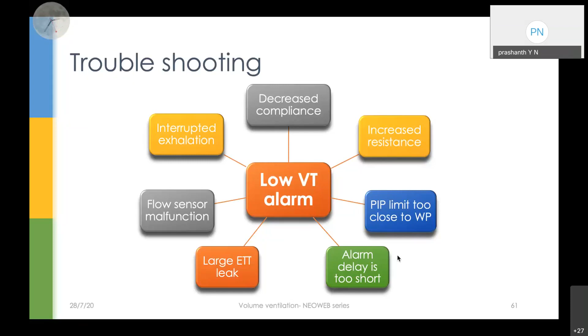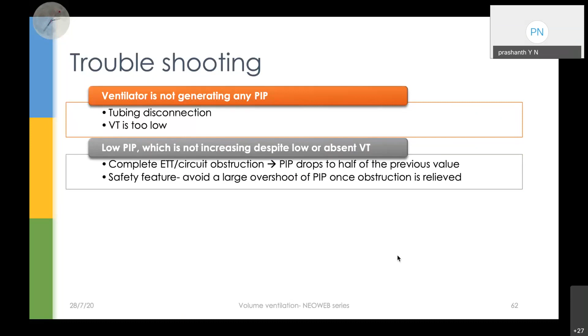All right. Other things could be, you also would have seen that a ventilator is not generating any PIP. Probably this will happen if the tube is disconnected or the set VT is very low. So there could be a low PIP which is not increasing despite low or absent VT. This is a safety feature in Draeger, where the trigger can sense a complete ET obstruction. Once it senses complete ET obstruction, where the volume is not going inside at all, it decreases the PIP to half immediately, so that an inadvertent increase in the PIP won't happen in the next breath. So we need to be watchful of it.